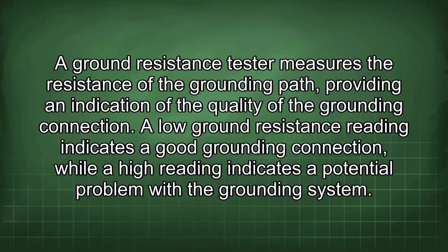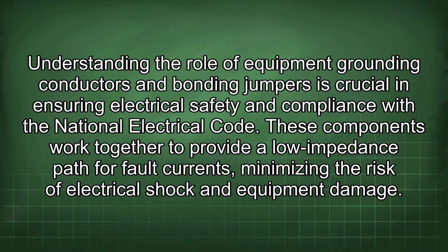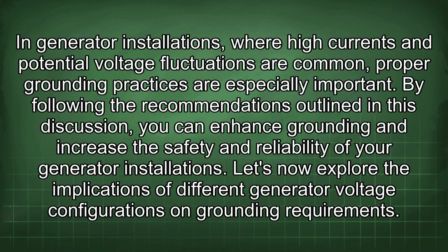the grounding system. Understanding the role of equipment grounding conductors and bonding jumpers is crucial in ensuring electrical safety and compliance with the National Electrical Code. These components work together to provide a low impedance path for fault currents, minimizing the risk of electrical shock and equipment damage. In generator installations, where high currents and potential voltage fluctuations are common, proper grounding practices are especially important. By following the recommendations outlined in this discussion, you can enhance grounding and increase the safety and reliability of your generator installations. Let's now explore the implications of different generator voltage configurations on grounding requirements.